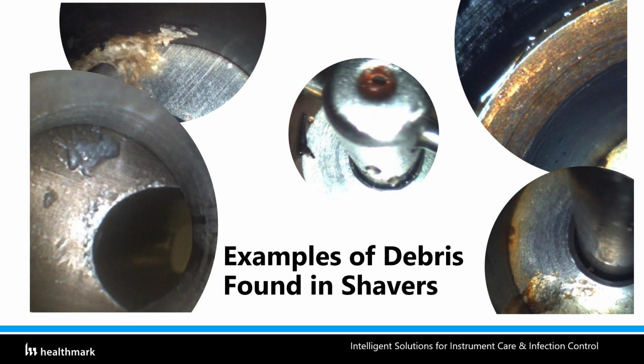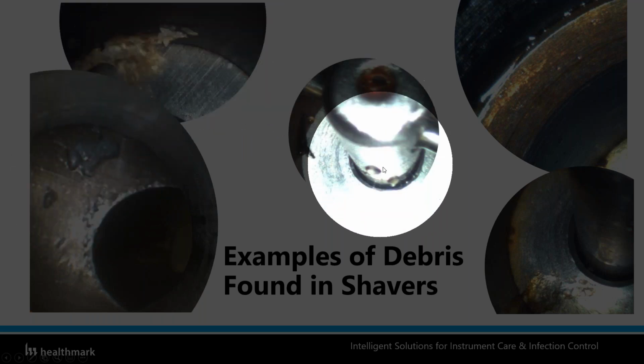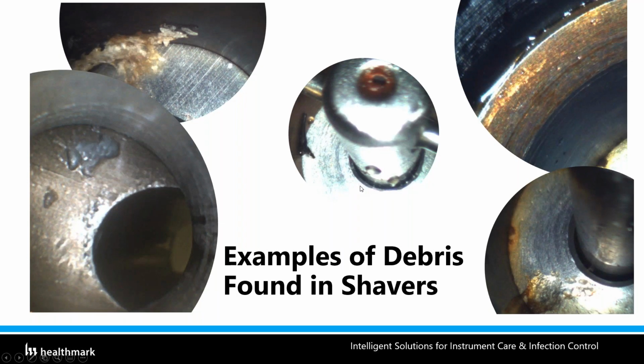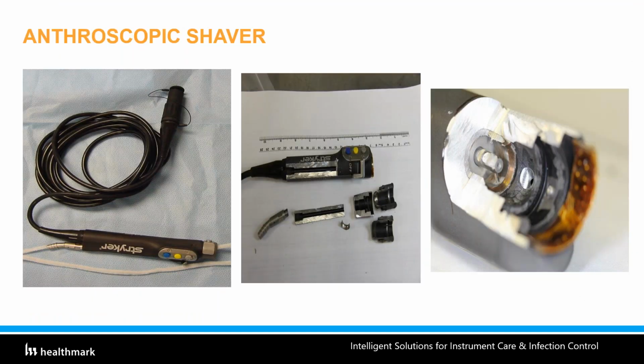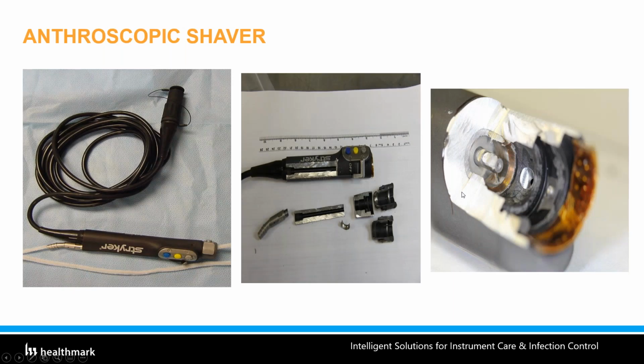So when we received those letters, we took one of those 2.7 mm endoscopes and looked inside the shaver, and we found similar items to what the CDC found within those shavers. Literally, we had 21 shavers, and when we looked at them, they all had something within them. So that was the shaver type involved with that issue. And then as we know with biomed, we want to know what's going on. We take one and take a saw and cut it in half to see what is inside it.